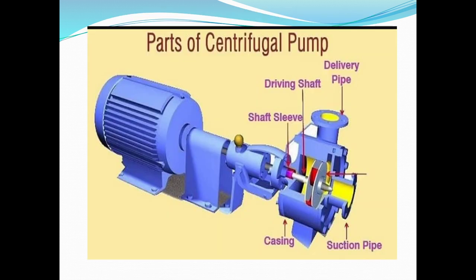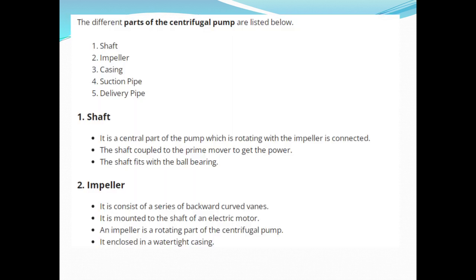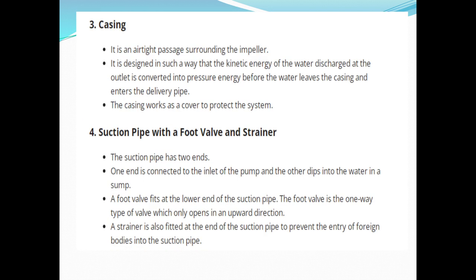We are using a casing, a suction pipe, a delivery pipe, a shaft and shaft sleeve — these are the important parts of the pump. The central rotating part is the impeller. The shaft connects power, and we use ball bearings. The impeller has a series of backward-curved vanes. This is the rotating part driven by the electric motor shaft. This is the watertight casing.